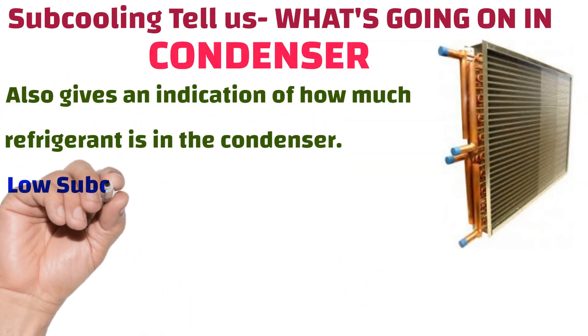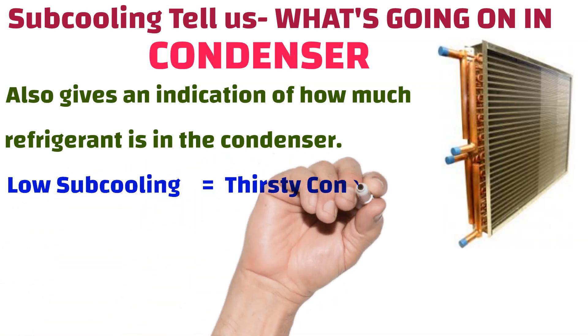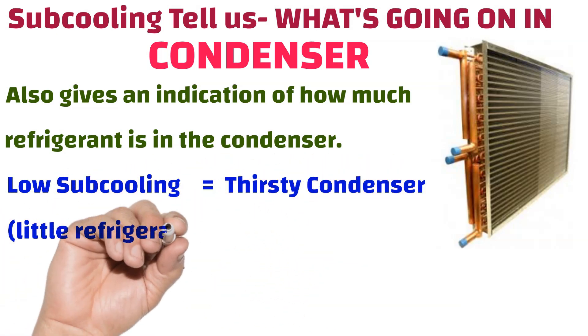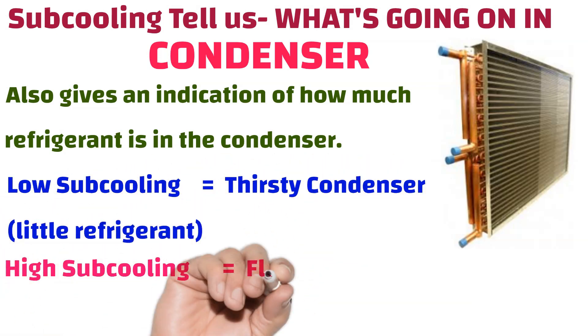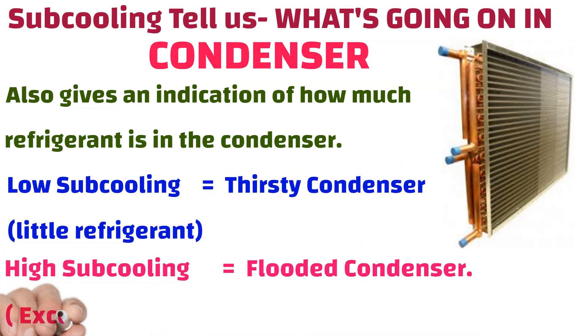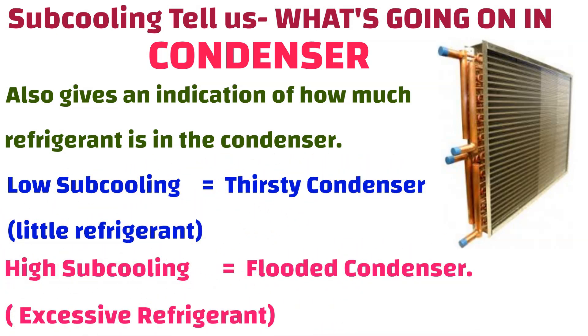Low sub-cooling equals a thirsty condenser, which means little refrigerant is in the system. High sub-cooling equals a flooded condenser, which means excessive refrigerant.